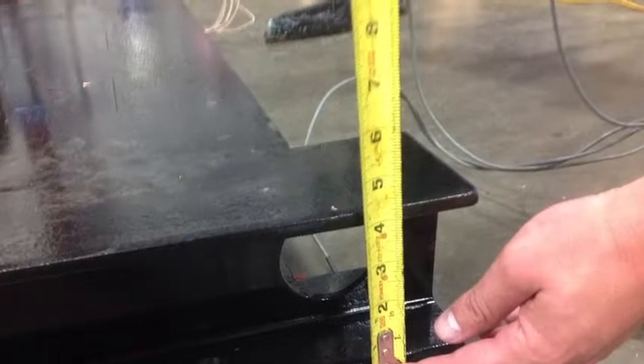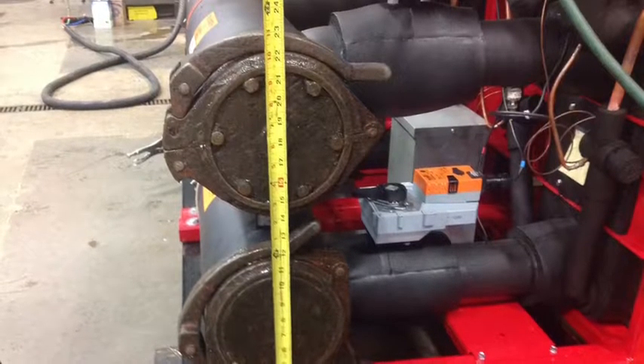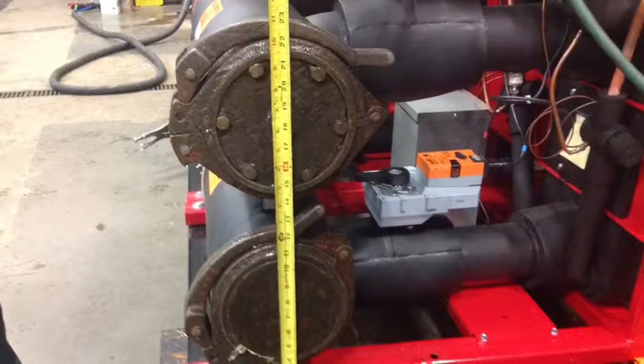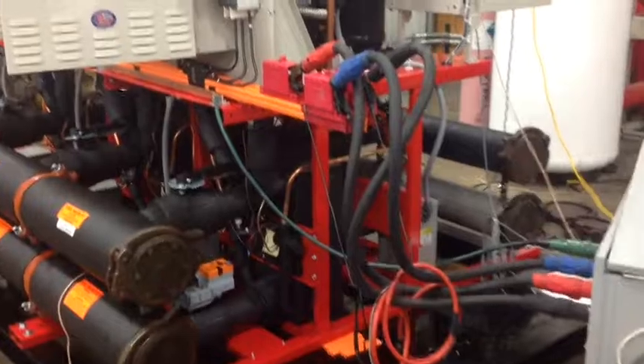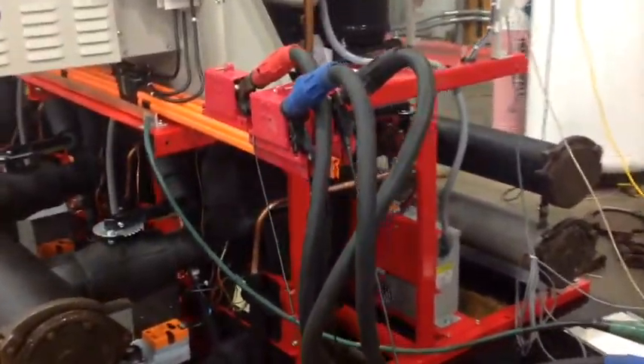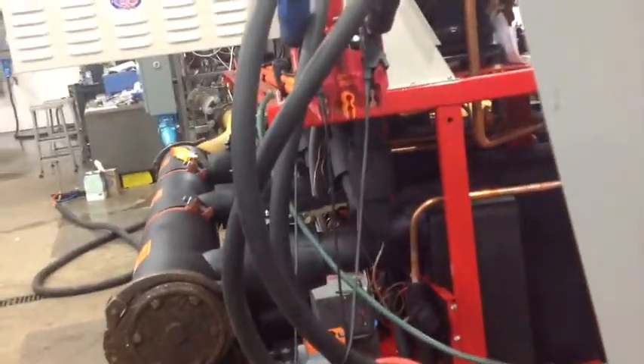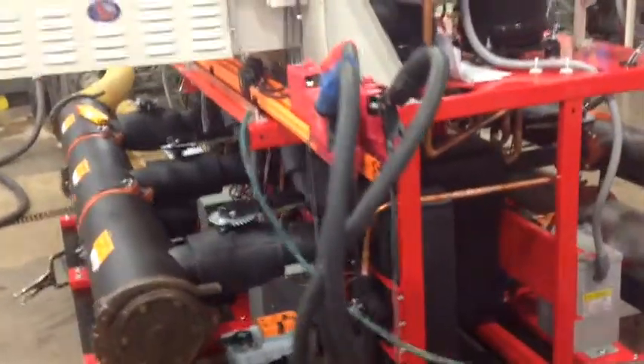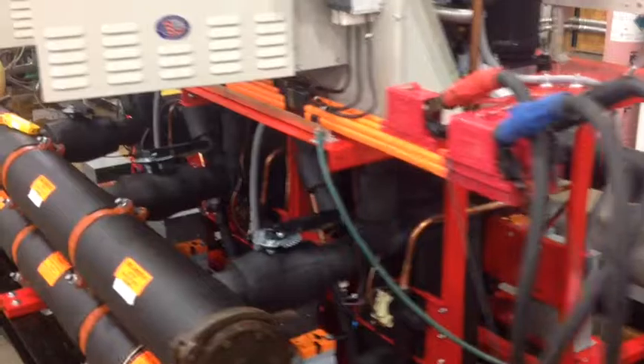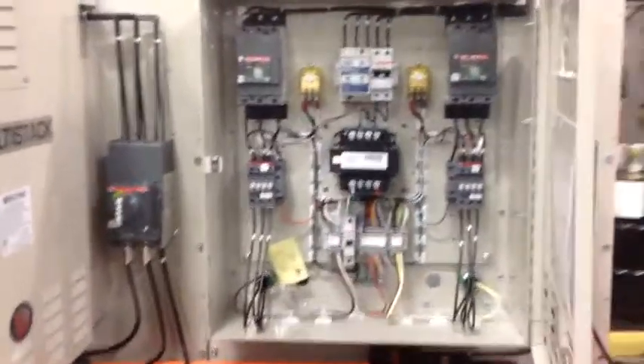Here's a close-up of the 4-inch measurement of our lifting frame, a photo that shows the height of the headers and the size of the water connections. Here's a close-up of the Busbar Extension that will create the single point power that distributes power to all 3 modules. As clarified in our submittal, this eliminates the possibility of a factory-provided door interlock disconnect switch. A disconnect switch provided by the contractor will be required.